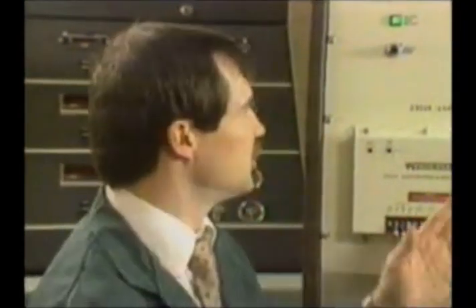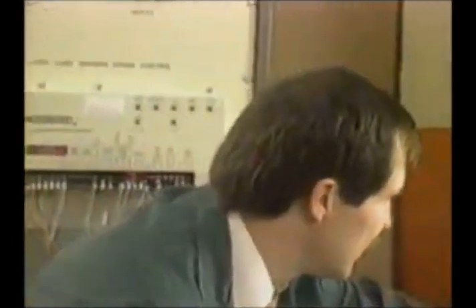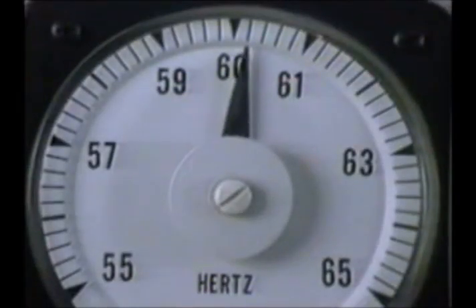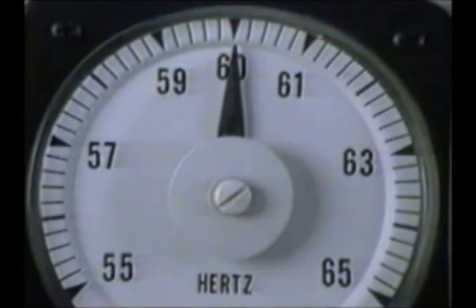Now the Caterpillar is turbocharged. So there is a slight time delay in the turbocharger getting going. So a little bit of that off speed is from the turbocharger. But you can see we're running at 60. Now if I take the load off, the speed will change and come right back to 60. That's very smooth. That's probably very acceptable to leave my settings at those points.